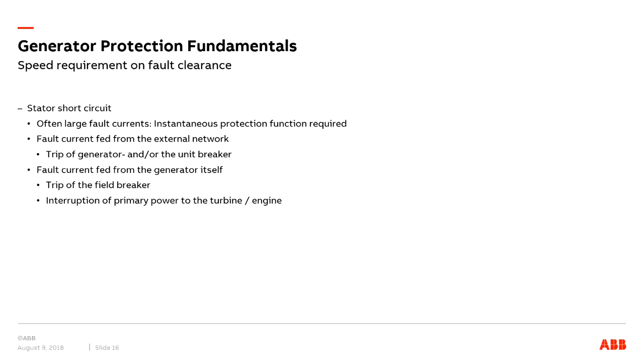The short circuit current fed from the generator itself is handled by tripping the field circuit breaker and by interrupting primary power to the turbine, like closing of the valves, etc. This contribution to the total short circuit current cannot be instantaneously cleared, even if the protection is very fast. That means the internal contribution cannot be instantaneously cleared.